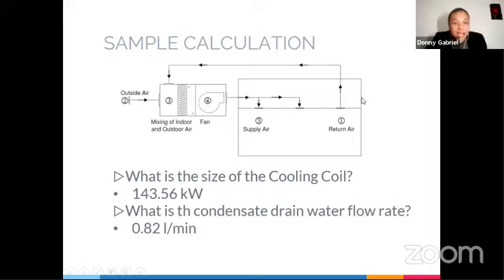From Sir Eric again. How to determine the drain pipe size from the psychrometric? Sorry, there's no pipe sizing on the psychrometric, but the water flow rate you will get from the psychrometric chart. So the pipe size, it's a different pipe calculation. We will discuss that on the next topic. That's a good topic to discuss. How to check the drain pipe size. So the drain pipe size is plumbing works because it's unpressured or no pressure required on the drain pipe. It's open to atmosphere.